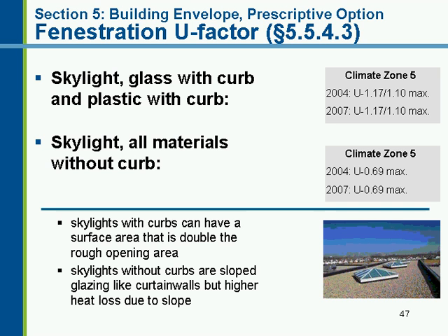For skylights, three different categories: glass with curb, plastic with curb. The U-factors: 1.17 for the glass with curb, 1.10 for the plastic with curb, no change from 2004. If it's a skylight without a curb, such as slope glazing that you would see in an atrium, it's a 0.69 maximum.